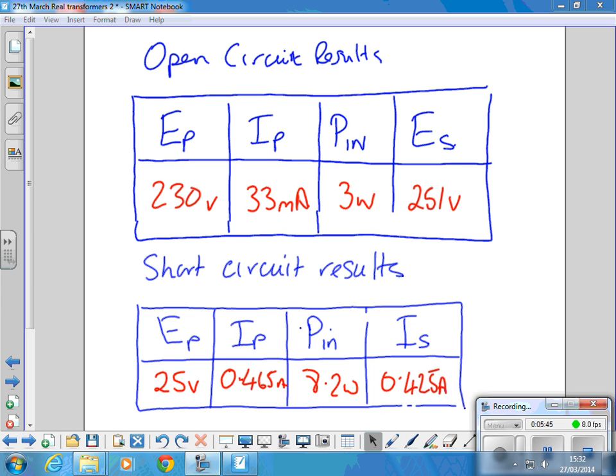And then the short circuit results. We short circuited the output, turned up the voltage on the input side until we got 425 milliamps secondary current. That's just under the maximum rating of the transformer. At that point we measured the power in as 8.2 watts. The input current was 465 milliamps, and that was at a primary voltage of 25 volts.